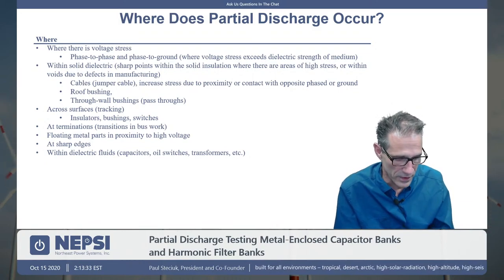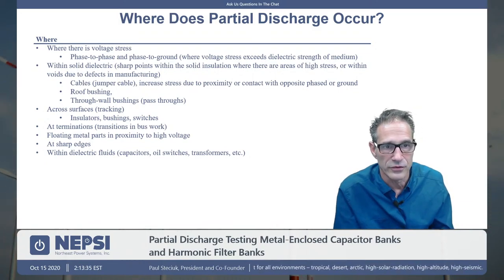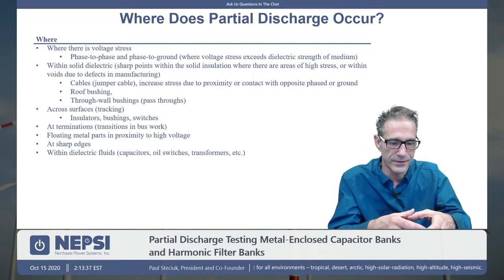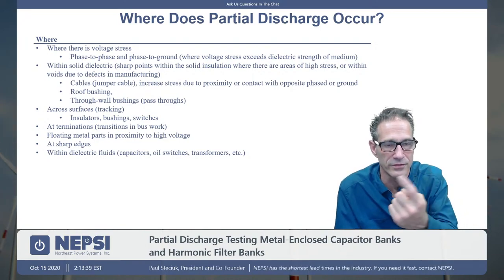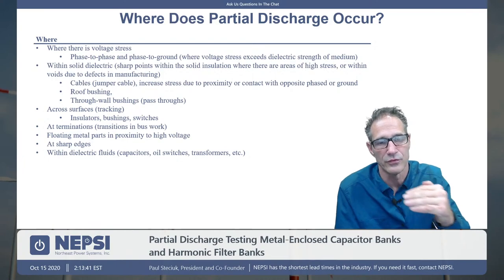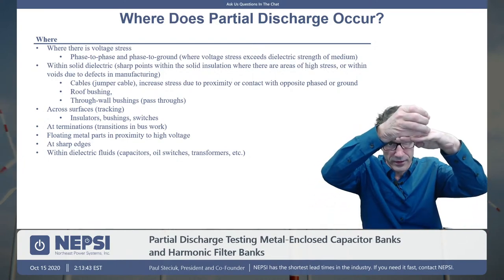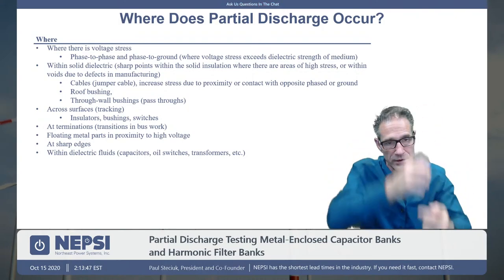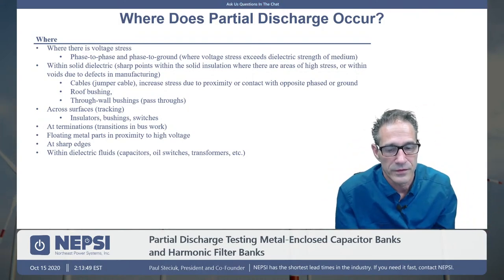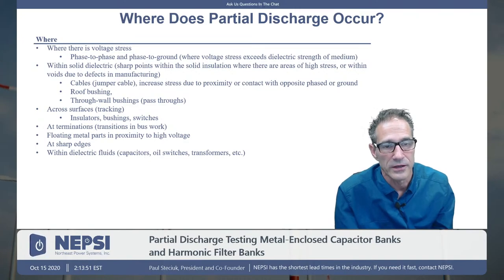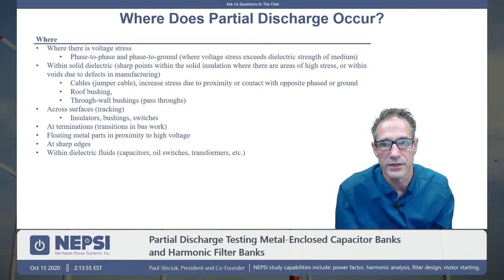And if you've ever done maintenance on a medium voltage piece of equipment, the insulator sometimes will become discolored, especially at the ends, where you have an insulator and you have an end. The sharp edges at the end can cause a lot of corona and tracking on the edge of the insulator.